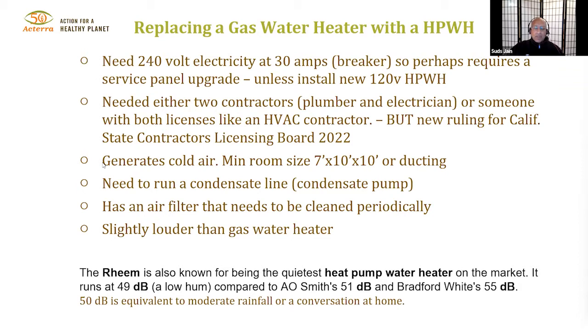If you were to take a heat pump water heater and put it in a small closet, what you're doing is cooling that space, sucking heat out of the ambient air. So you can imagine the more heat you're sucking out, the colder that room gets, and the heat pump has to work harder and harder to extract heat. So they have minimum room sizes for installing these.